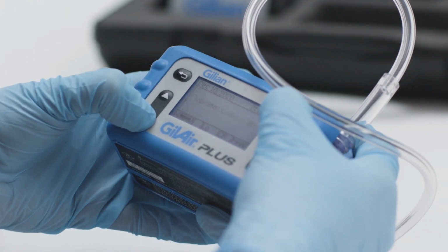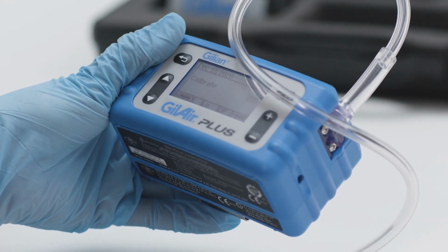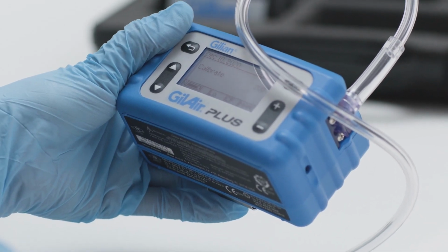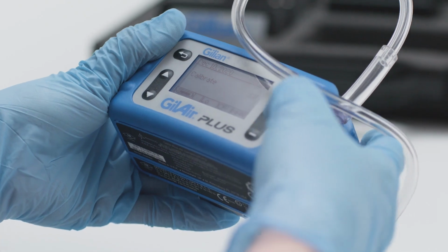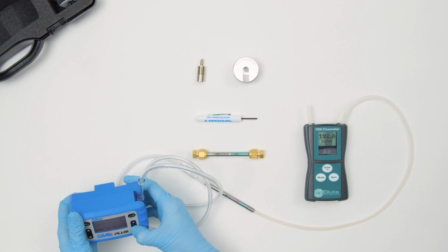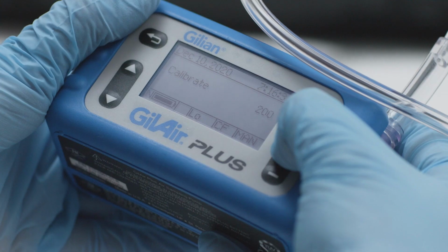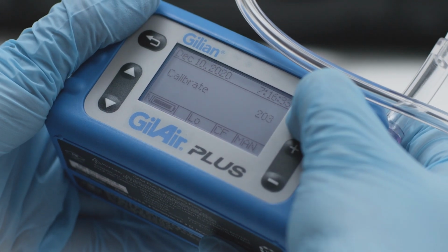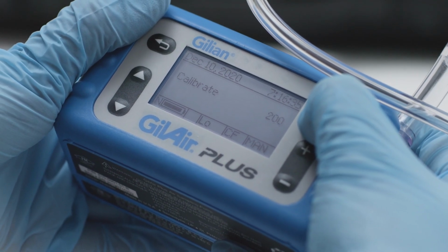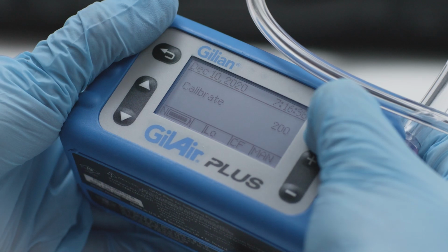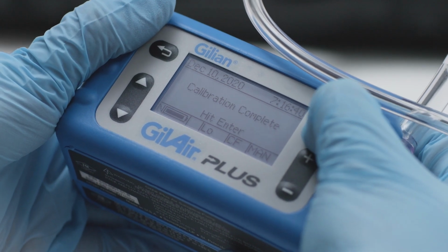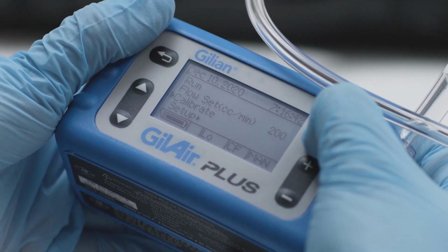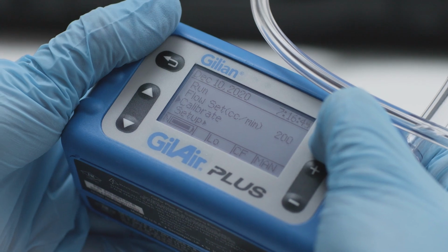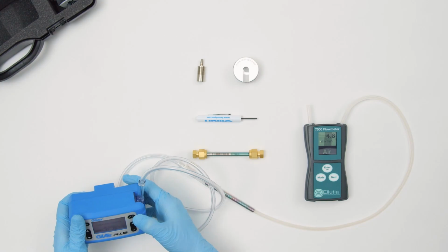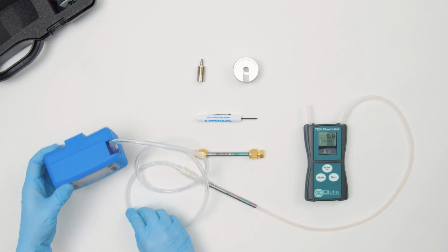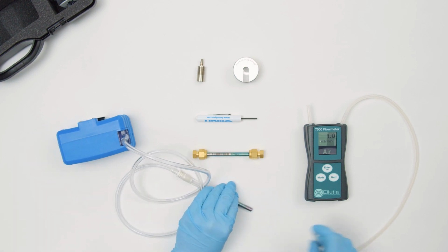Select Calibrate from the Start menu. The display will indicate the set flow rate and the pump will begin to run in calibration mode. Use the plus and minus keys to adjust the flow rate on the display screen until it matches the flow meter, then press Enter. The pump will adjust based on the value that has been input. This step may need to be repeated until the pump flow matches the flow meter. When the desired flow rate has been reached, press Enter to set calibration and remove the calibration tube from the adapter. The pump is now ready for sampling.